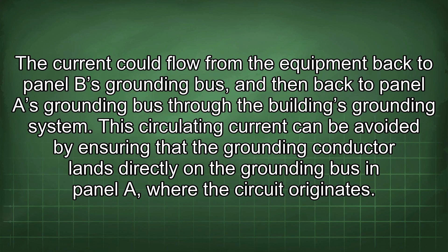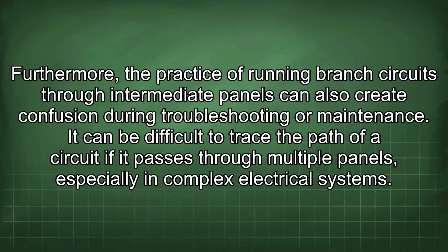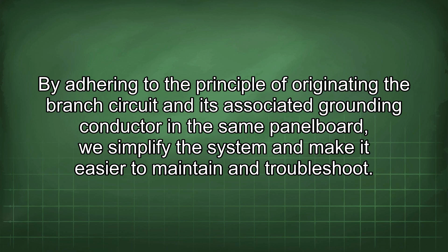Furthermore, the practice of running branch circuits through intermediate panels can also create confusion during troubleshooting or maintenance. It can be difficult to trace the path of a circuit if it passes through multiple panels, especially in complex electrical systems. By adhering to the principle of originating the branch circuit and its associated grounding conductor in the same panel board, we simplify the system and make it easier to maintain and troubleshoot.